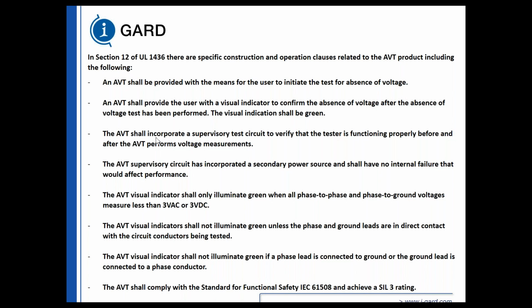The absence of voltage tester shall incorporate a supervisory test circuit to verify that the tester is functioning properly. This is done internally. It's testing itself after you've pressed the test button to ensure that it's properly connected, all circuitry is functional in order to come up with the green LED. So you have to satisfy that the tester is working properly, it's connected properly, and you have less than 3 volts. The supervisory circuit incorporates a secondary power source. We have a supercapacitor, which is our secondary power source. So we have to test the tester to a known power source, and our known power source is the capacitor.